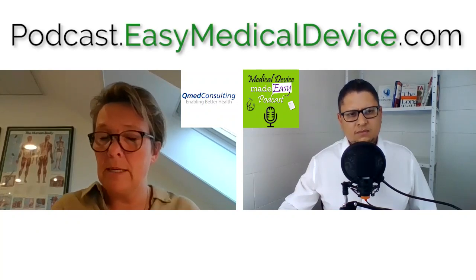And there are tools out there. People are used to doing this on good sites. And there are other ways also. It says post-market clinical follow-up activities, so it's not just surveys and clinical investigations. With these different kinds of devices, try to put up the rationale. That's one of the things the notified body is very interested in: that you argue or come with a justification for the method that you are choosing. As long as you have a good reason and it's solid, I would go for it.